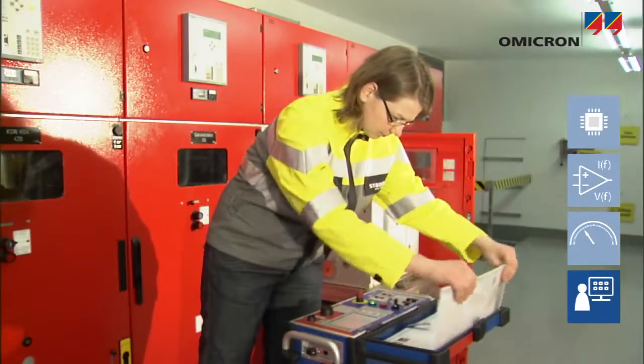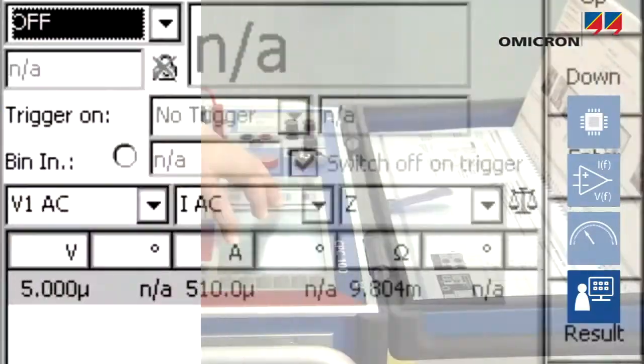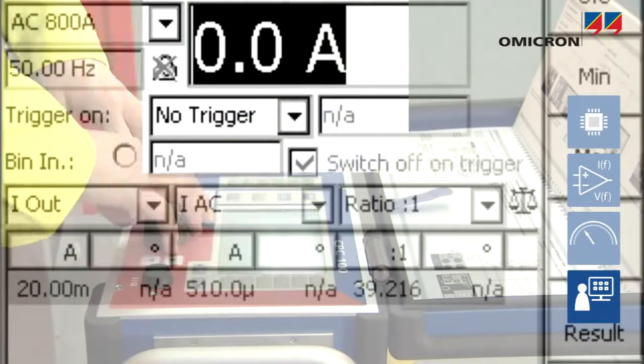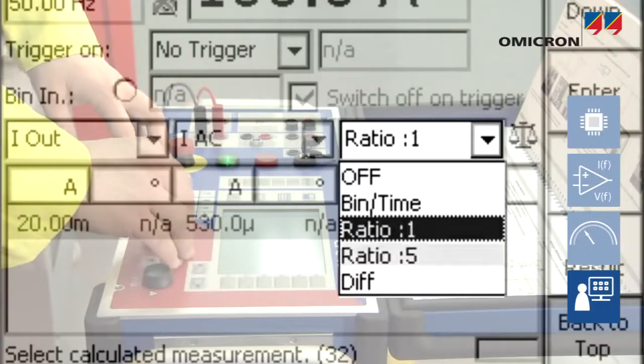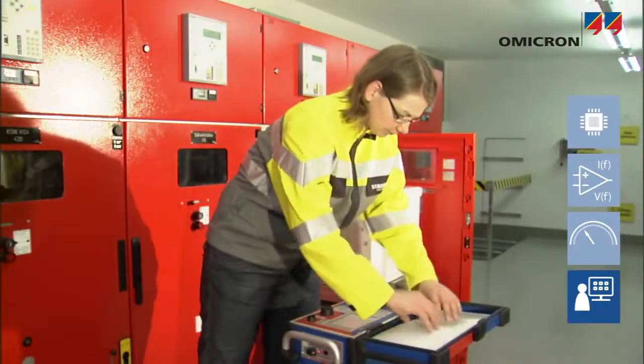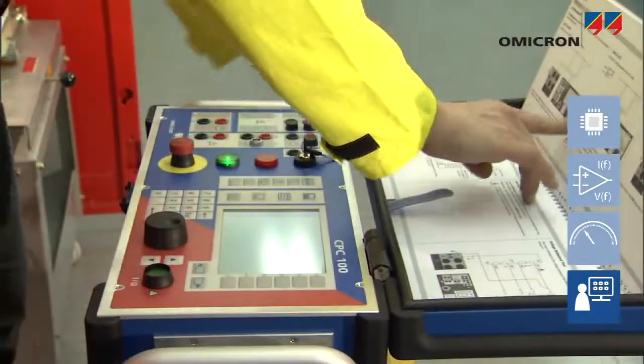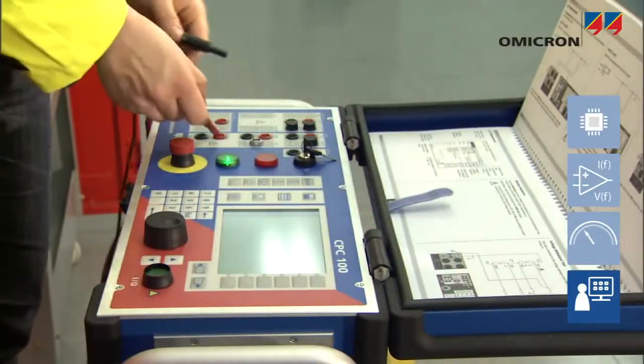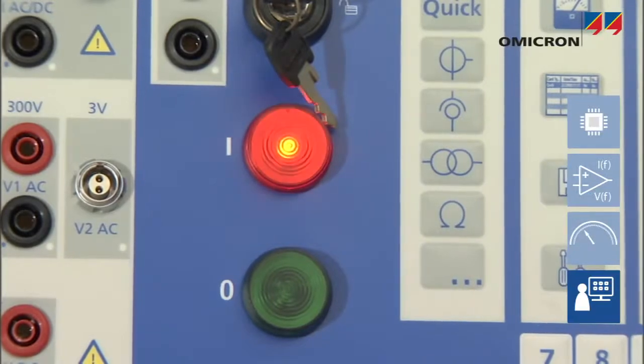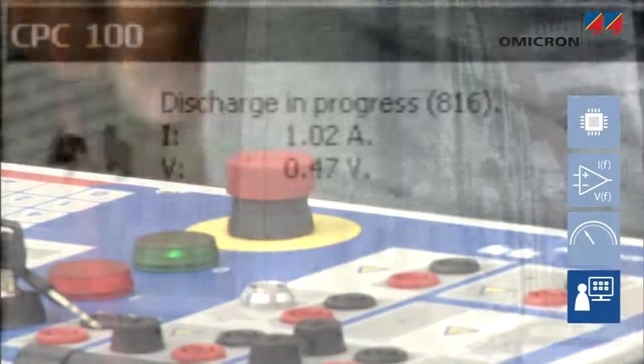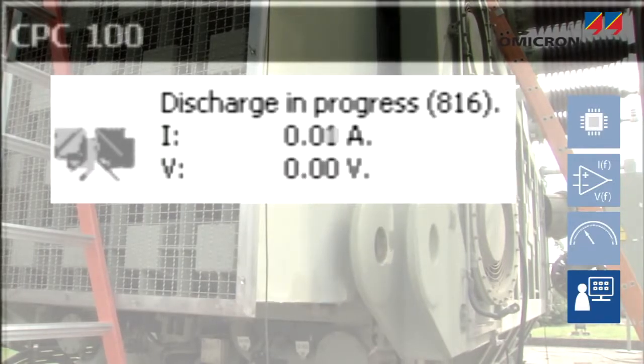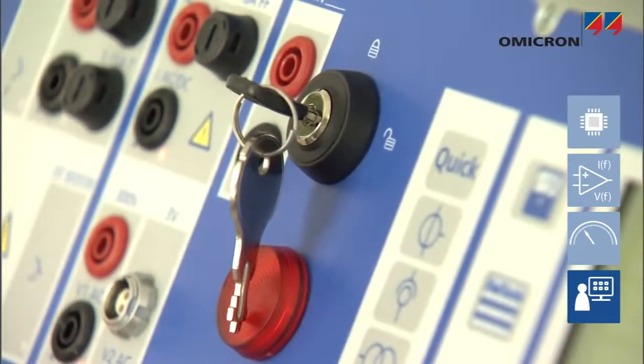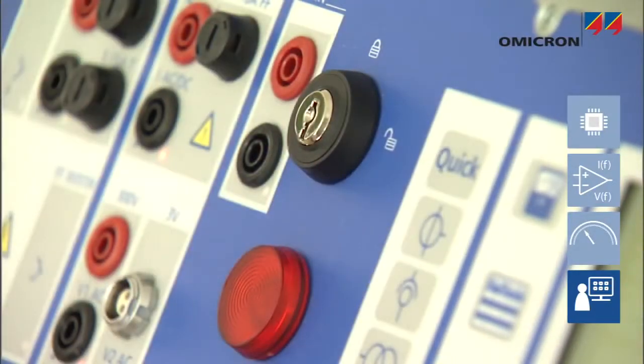The built-in multi-language user interface allows selection of the test mode, entry of the voltage or current value, and control of the measurement. An integrated manual located in the top cover supports users with setting instructions and wiring diagrams. Flashing lights on the front panel clearly indicate the injection of voltage or current. An emergency off button immediately stops all injection and discharges the energy stored in the test object, such as a transformer winding. The CPC can also be locked to prevent unintended activation.